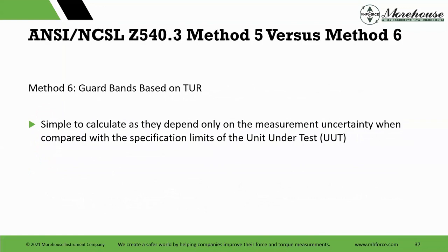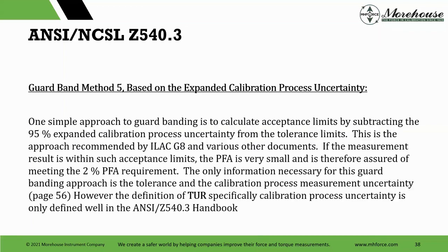We talked about the ILAC G8 rule. Here's method 6 that we're going to talk about now, and the pros and cons of these two methods. I do happen to like the standard. First, it's free. All of ILAC G8 is free, and the handbook, if you're an NCSLI member, you can pull it. Method 6 in the handbook is a less conservative approach. It's simple to calculate, and it depends on the measurement uncertainty compared with the specification limits of the unit under test. This is where it's critical because it uses TUR. Then we have guard band method 5, based on the expanded calibration process uncertainty, which is the bottom of the equation. It's another simple approach. It's basically recommended by G8, but they opened the limits up a little more, and you can look at that.